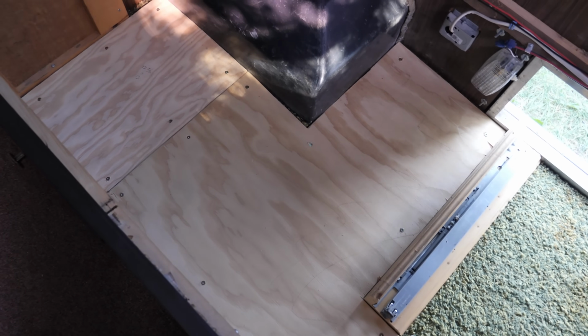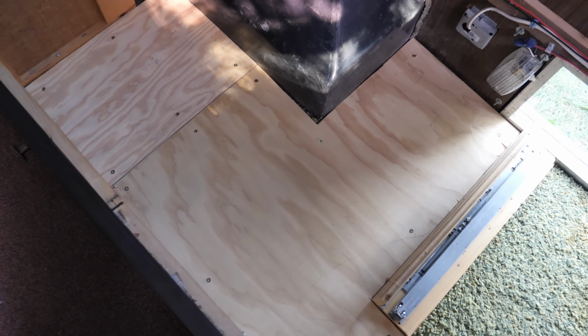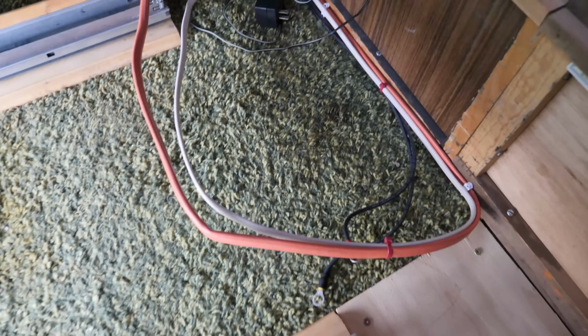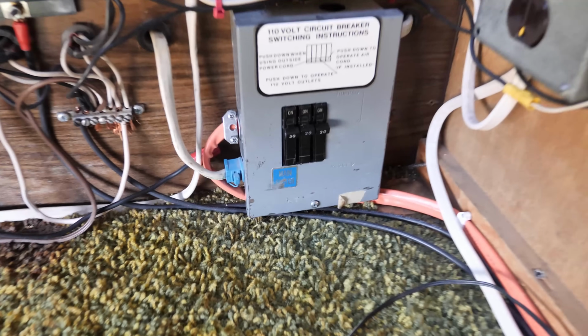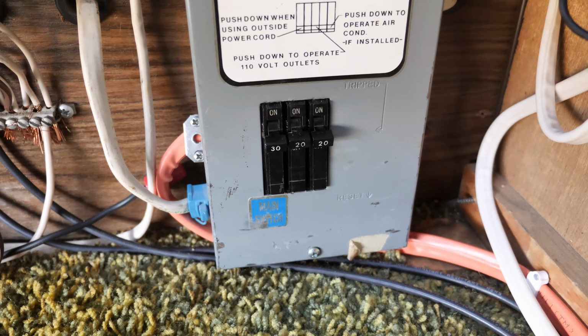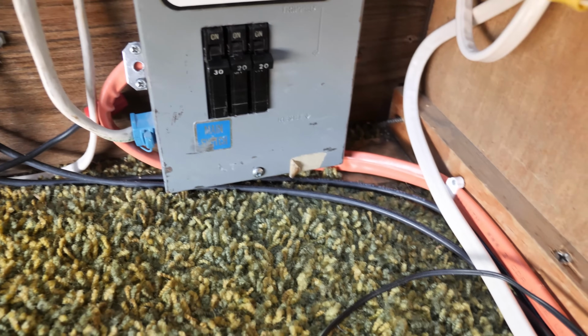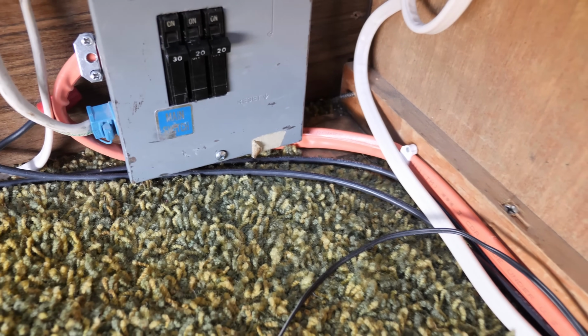We put down some plywood over here where the batteries and inverter are going to go, and over here we also wired in the AC. Basically, we're coming out of this 30 amp circuit breaker through the 10 gauge wire, which is the orange wire, and we got it run along the side here, coming out right here.